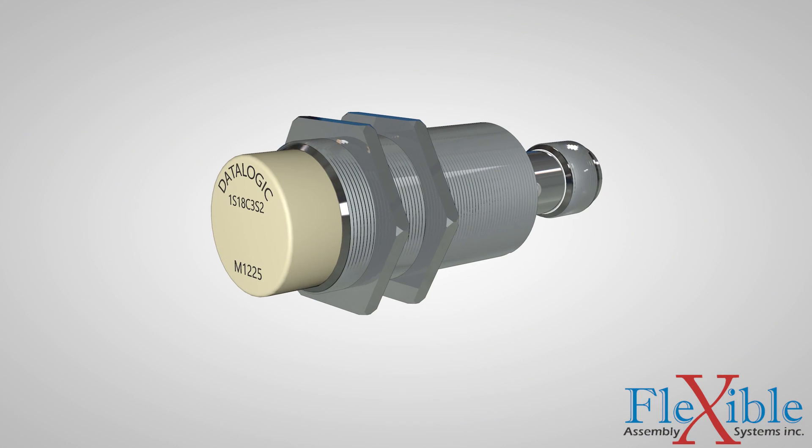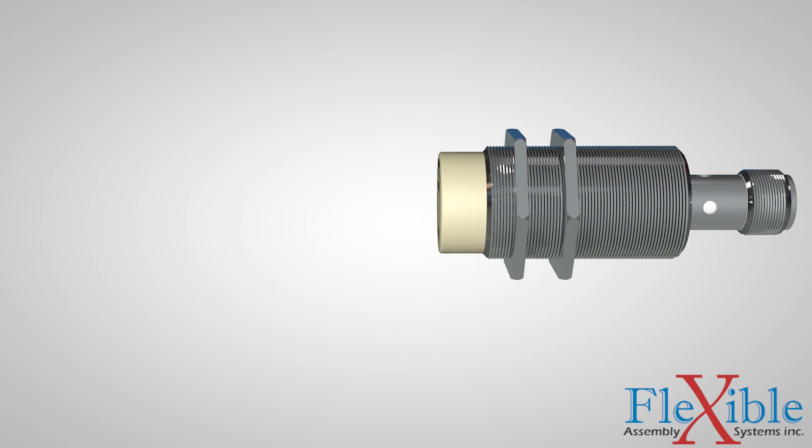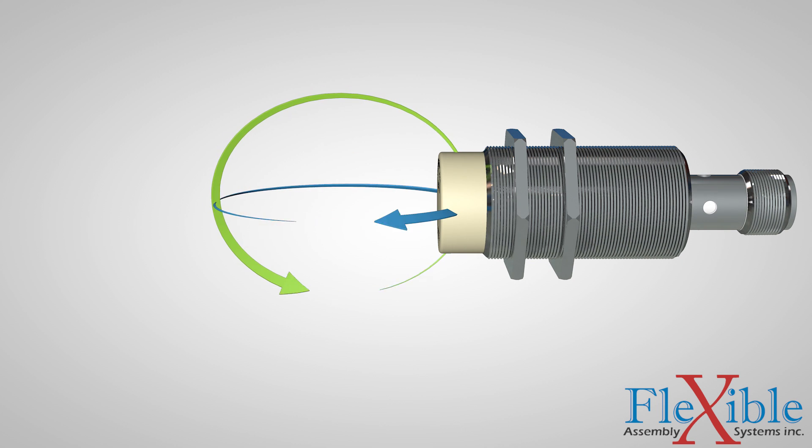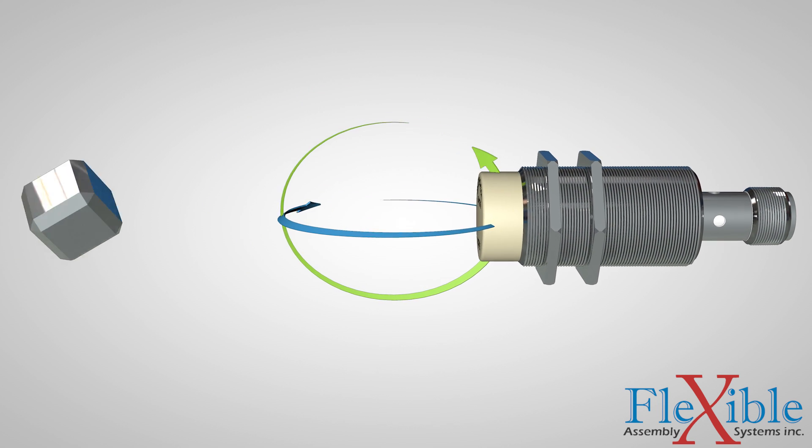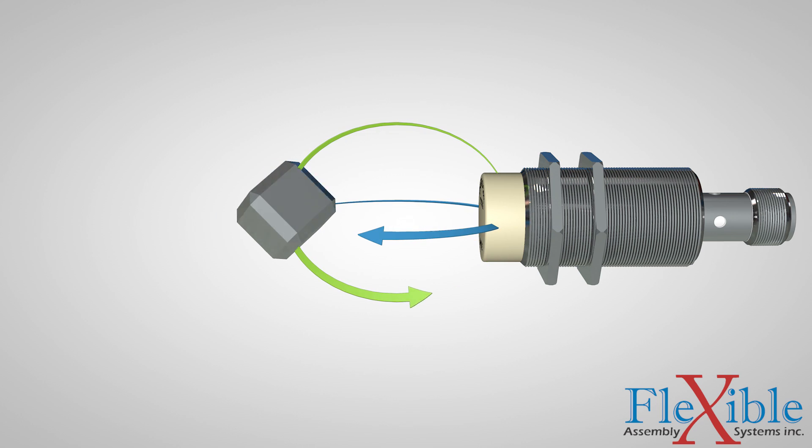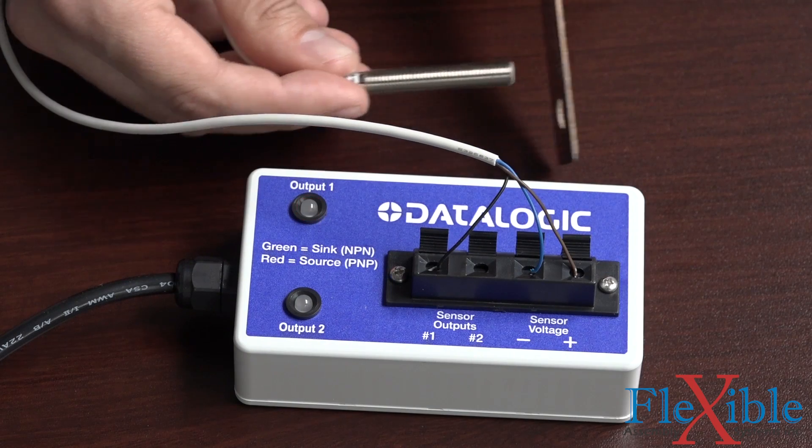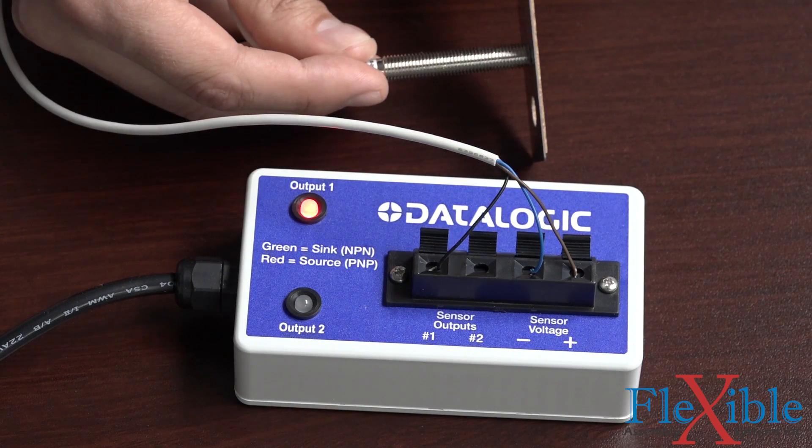An inductive sensor is a non-contact sensor that uses a coil and an oscillator to generate a magnetic field around the sensing surface. When a metallic object enters the operating area of the sensor, there is a dampening of the oscillation amplitude, which is read by a threshold circuit and changes the output.